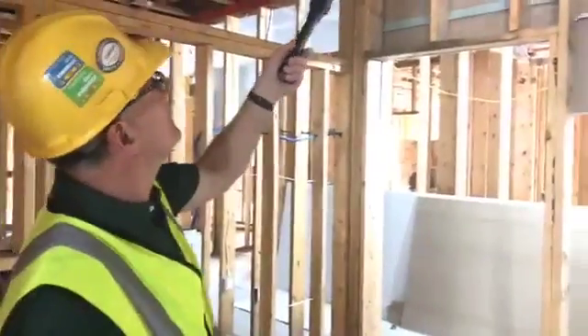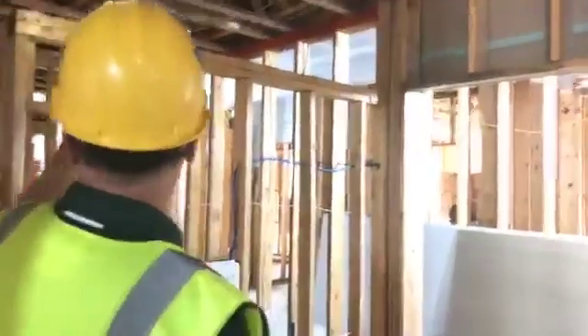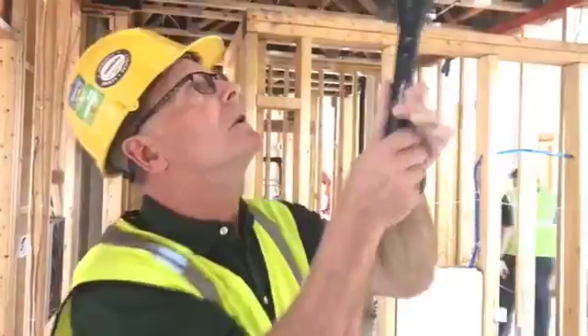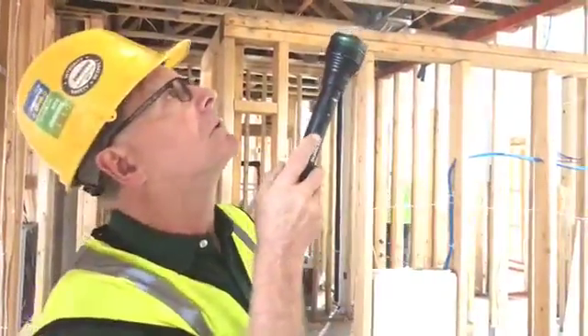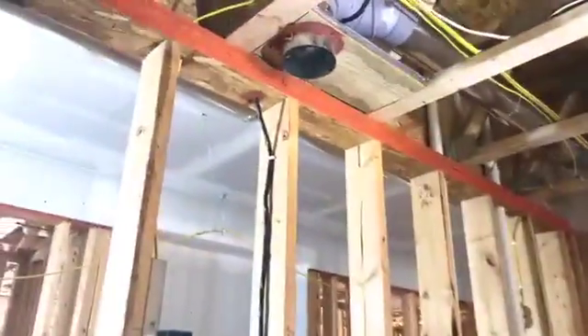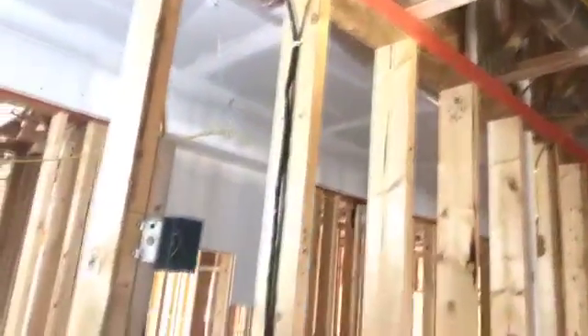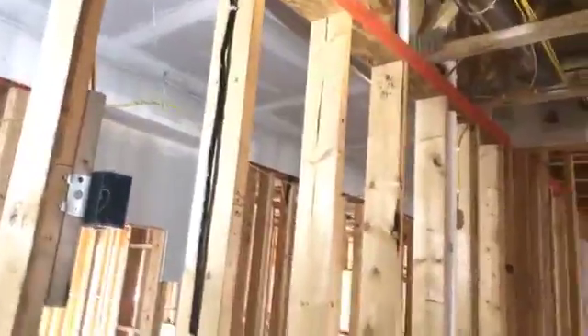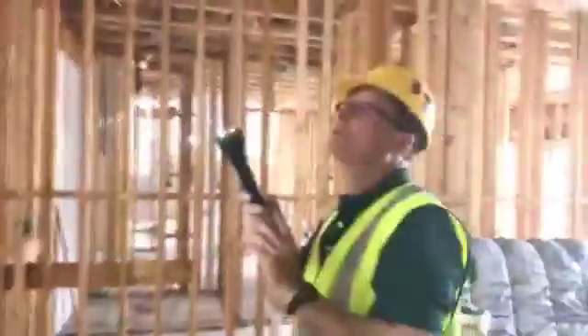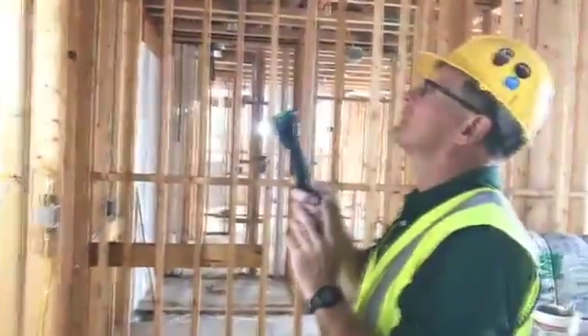We found leaks in little simple details, but again, it did pass because they did a good job on the onset. This is where we have the biggest problem with Energy Star and with that requirement under V4: the duct leakage on forced air systems. They've already got this one piped in for the range exhaust. They went the extra mile and sealed all the pores, all the connections, and that goes all the way out. We have to hit 100 CFM flow. We should be able to hit it with the design of this duct system.